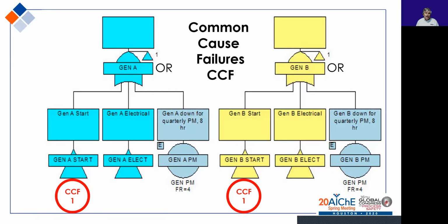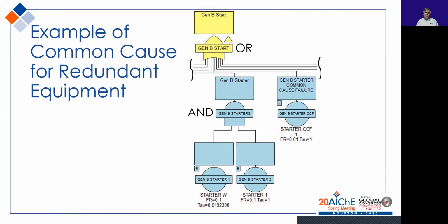It turns out we have common causes farther down in the tree, CCF1, that can prevent both generators from starting. Likewise, we have common causes, CCF2, that can prevent both generators from producing the electrical power that's needed. An example of common cause for redundant equipment is, remember we had 2 starters and 2 batteries for each generator.